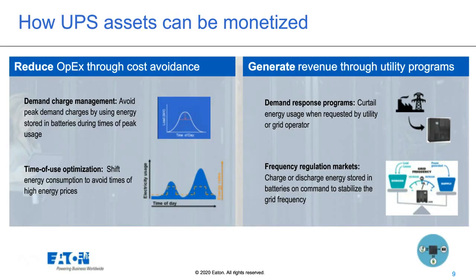So let's get specific about how we might use a UPS and battery system to monetize that investment and get some revenue stream from it. On the left-hand side of the slide, we see that we might want to reduce operational expenses through cost avoidance. One of those possibilities shown here is demand charge management. Demand charges are basically set typically based on the amount of peak energy you may use, maybe only once a year for 15 minutes, but that sets a recurring monthly demand charge that gets tacked onto your utility bill. This may not sound like a huge thing, but some of our data center operators tell us that 30% or more of their electric bill every month is comprised of demand charges.